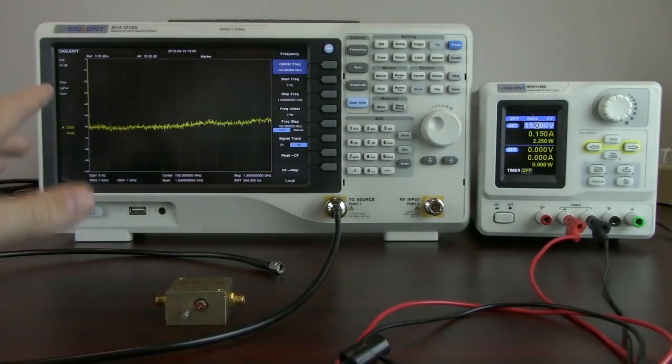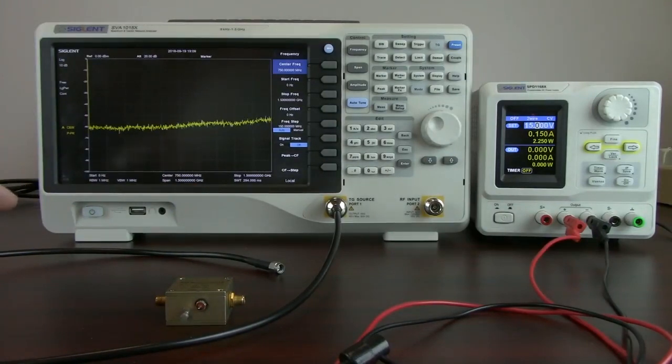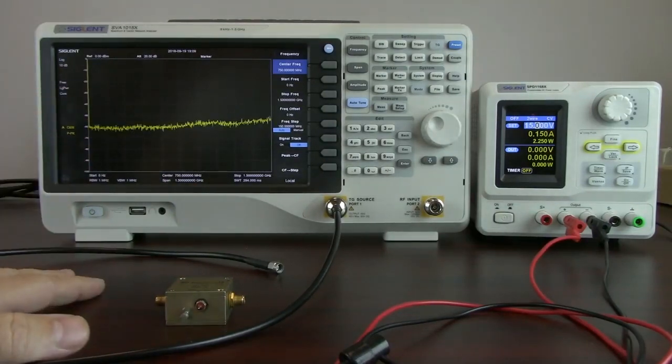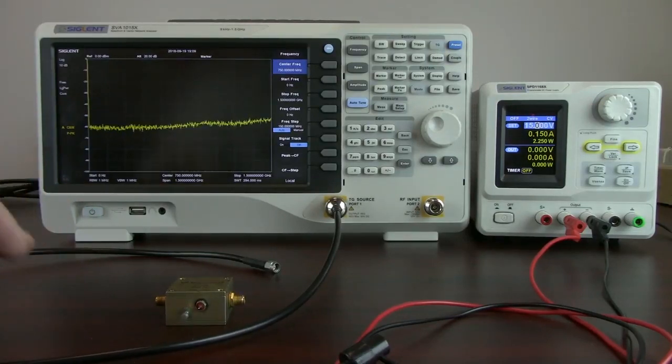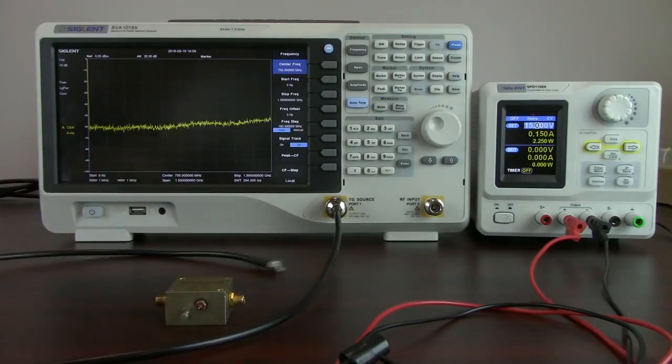I'm going to be using the SVA1015X Spectrum and Vector Network Analyzer. This actually has the VNA option or Vector Network Analyzer option, and that's the option we're going to be using to perform this VSWR test.